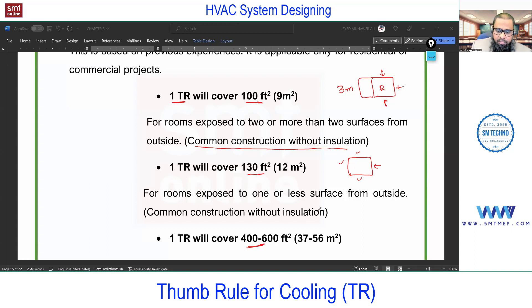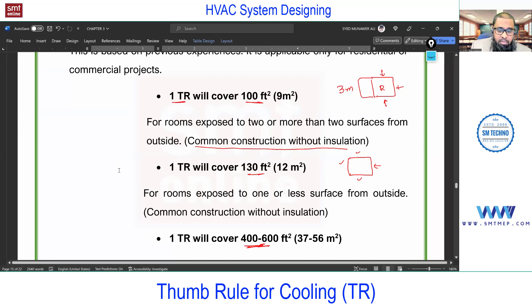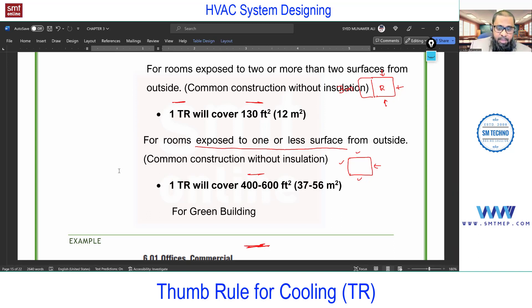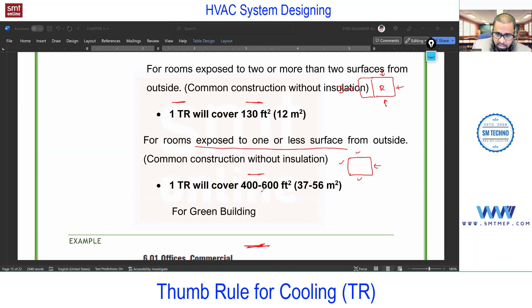This older rule is now outdated. In actual practice, one TR will cover 400 to 600 square feet. I'm talking about a standard insulated building — a green building or standard project. For standard or high-class projects, you'll find insulation in the walls and roof. Even for small projects in India, roof insulation is common since the top slab is exposed to the sun. For green or standard insulated buildings, 400 to 600 square feet per ton is a very efficient rough estimate.